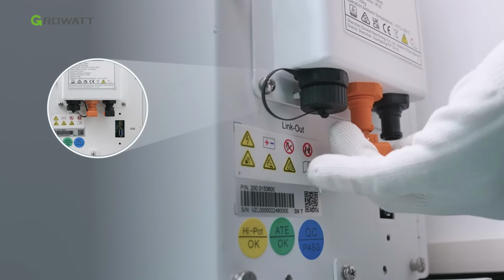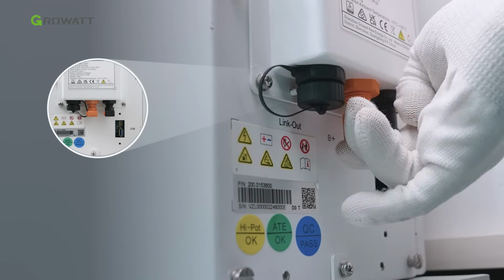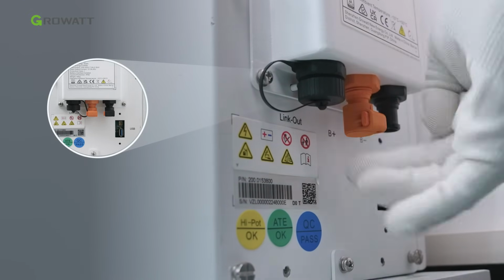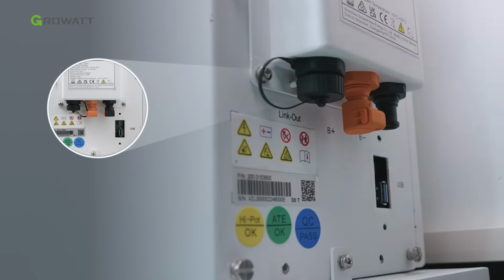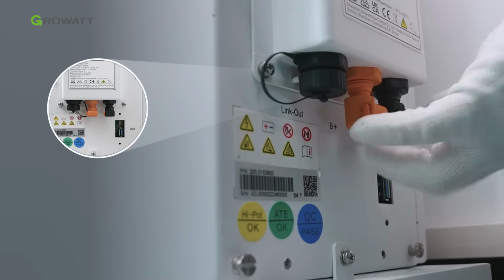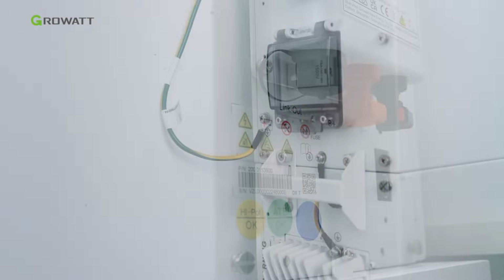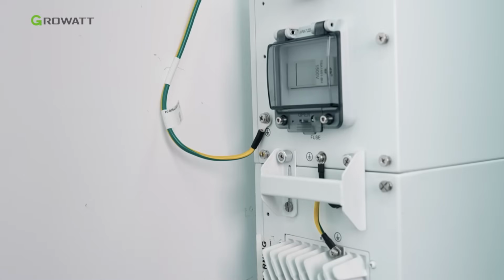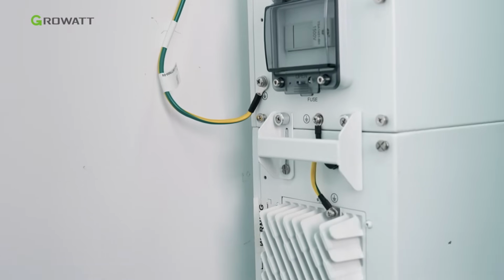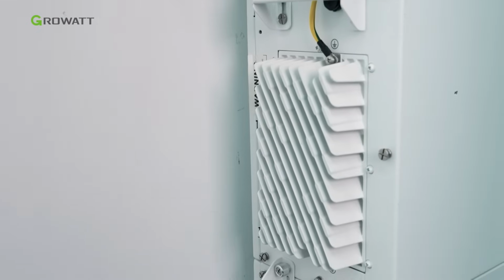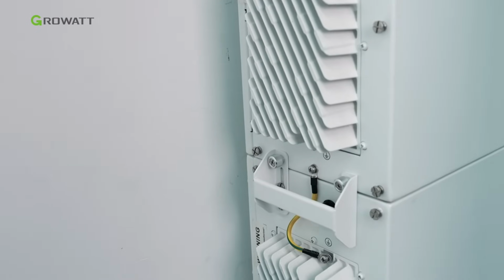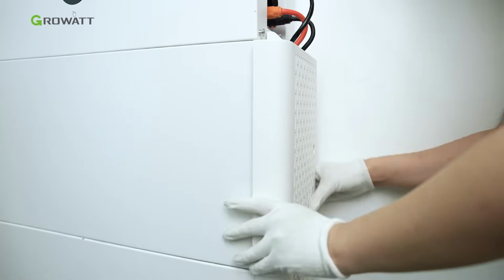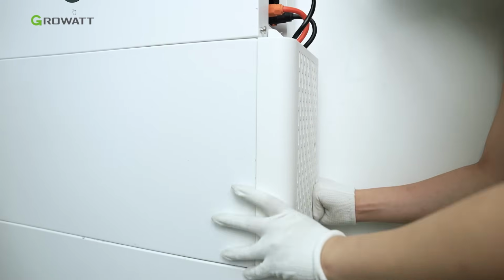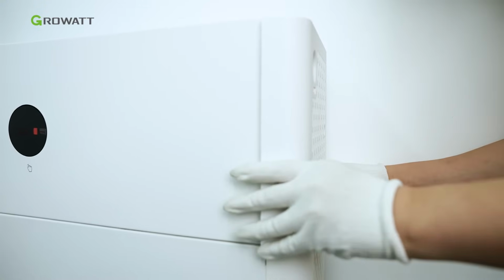Don't forget to connect the dust caps to the link out communication port, the positive port, and the negative port of the bottom battery module. Besides, please remember to connect the grounding cable of the APX battery system by passing it through the protective rubber ring and then to the earth point. Place the side protection flaps over the sides of all battery modules and power module to complete the installation.